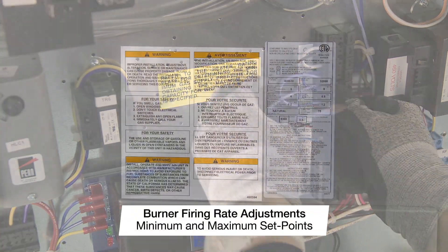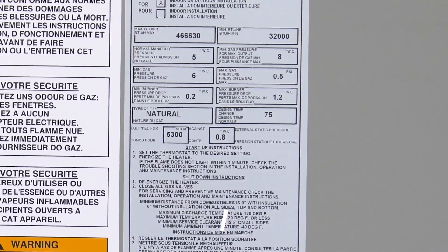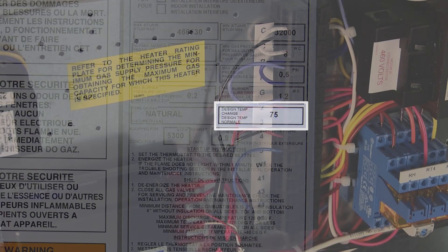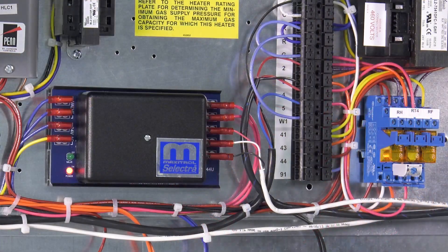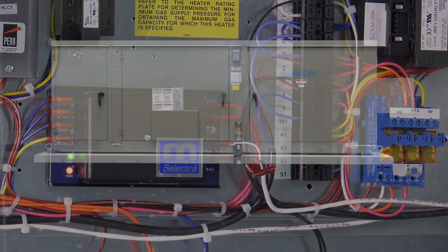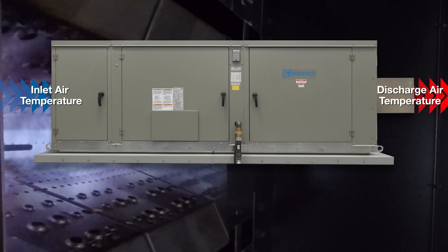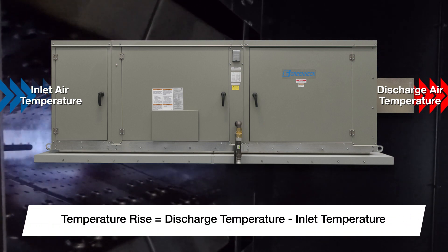Now we will set up the minimum and maximum firing rates. Begin by setting the maximum firing rate to the design temperature rise located on the heater rating plate. Re-energize terminal W1 to initiate the call for heat. Send the unit into high fire by removing terminal 3 from the Maxitrol Series 14 or 44 amplifiers. Monitor the unit's discharge temperature as well as the inlet air temperatures to calculate and adjust for the design temperature rise.